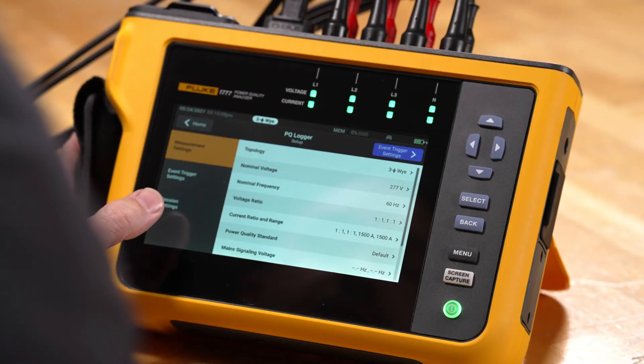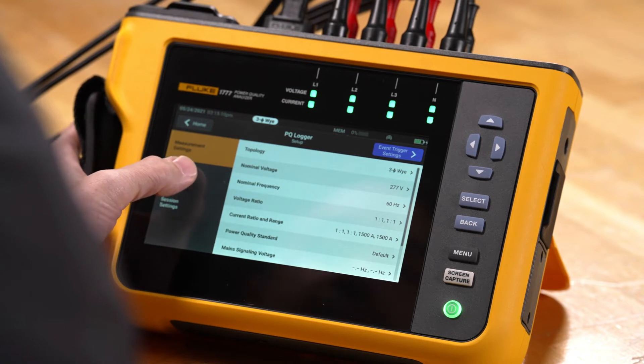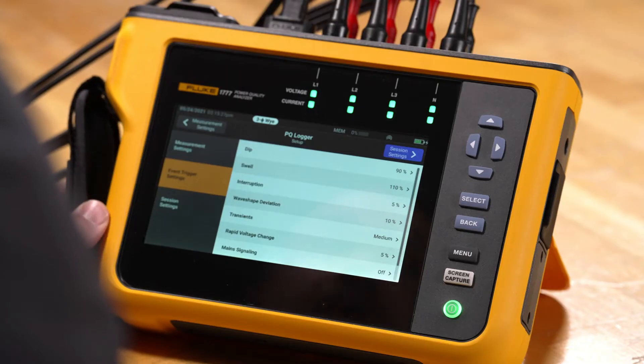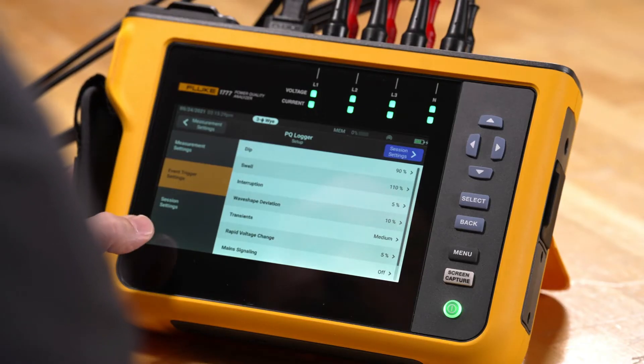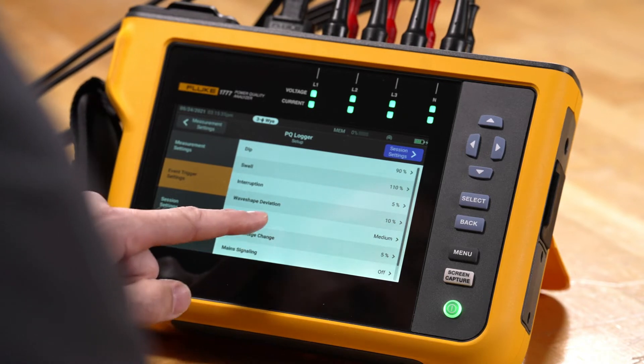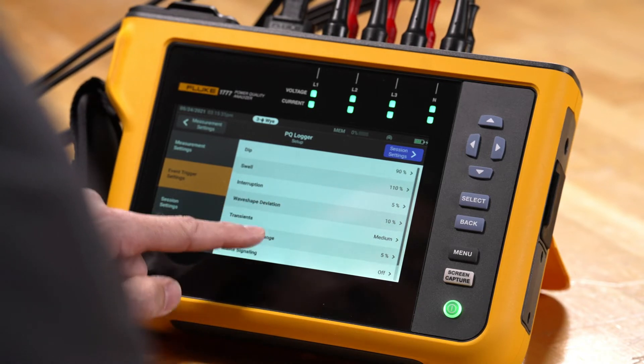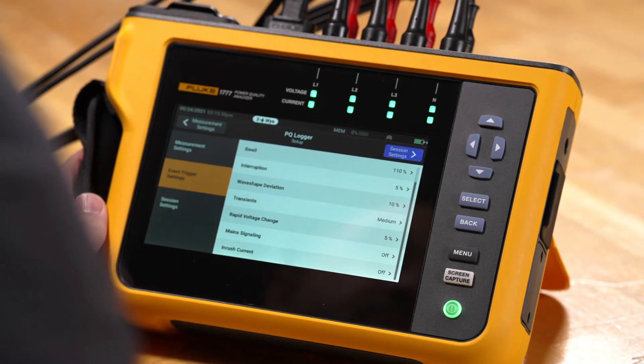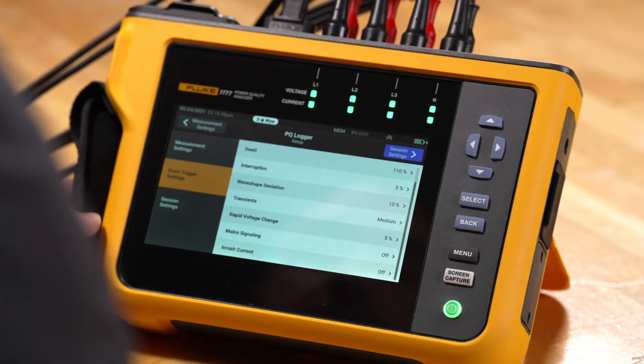We're going to go down and take a look at our event triggers. Event triggers are already pre-set up based on a power quality standard for you, so you don't actually need to modify these unless you want to make changes from a standard. We also have the ability to scroll down and make modifications to the transient triggering. We have rapid voltage changes, as well as inrush capture.